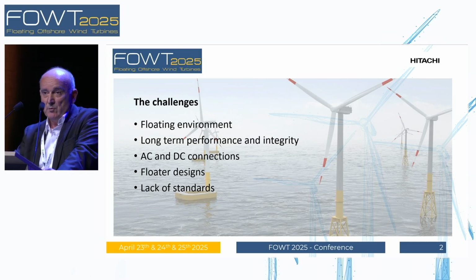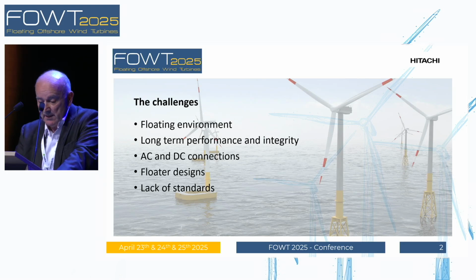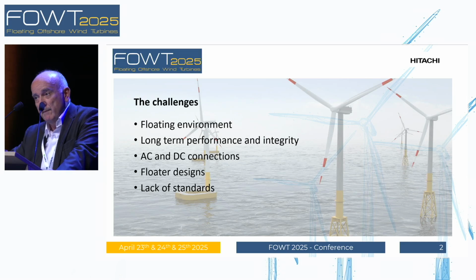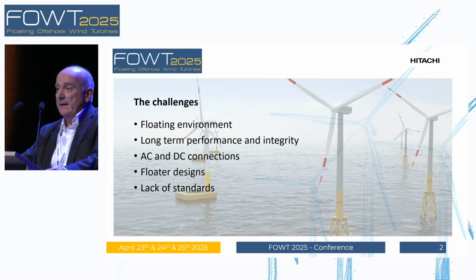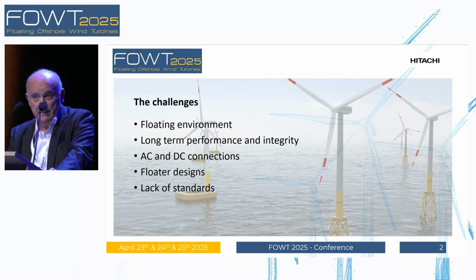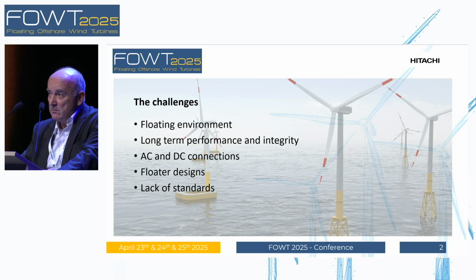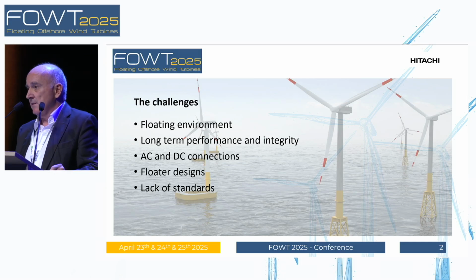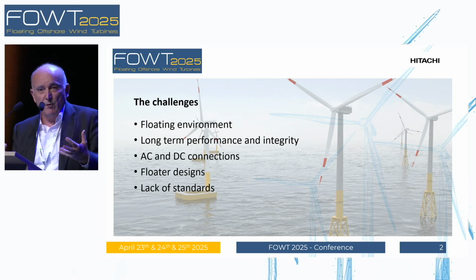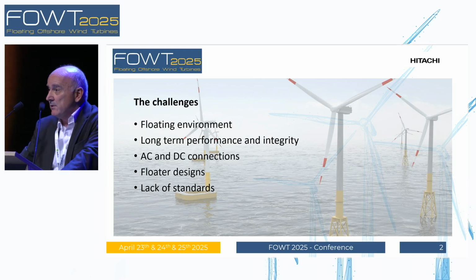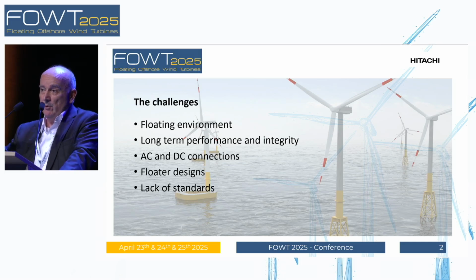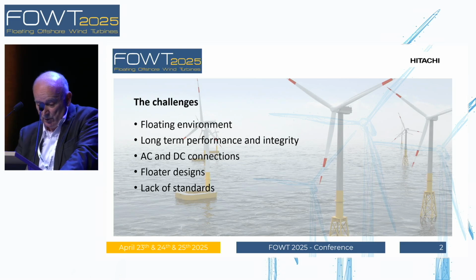The third challenge we face is the technologies. We are focused right now on AC-connected substations, and that's what we're working on. But we know that to tap the full potential of floating, we have to go further and deeper in the sea, and the size of those wind farms will get bigger. That calls for HVDC, which means we have to start developing floating HVDC now. The challenge is that the number of components we have to prepare and design for this new mechanical environment is multiplied by 4 to 5, which tells about the level of complexity we are facing.